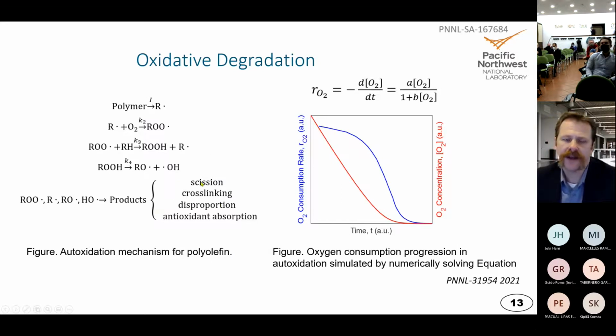In thermal and radiation aging as well, for these polymers, the major mechanism of degradation is oxidative degradation, where the polymers, the hydrocarbons, react with oxygen in the atmosphere, and reactive radicals get generated in the polymer from the radiation or from the heat, and those react to break up the polymers and change the mechanical properties. The major concern is that they embrittle the polymer, and then if there's an accident in the plant, they won't perform their function. The oxygen gets consumed in that reaction. So one measure of aging that's been proposed that might track closely with aging, even at mild aging, is the consumption of oxygen in this reaction. If you're having this oxidative degradation, it doesn't happen without consumption of oxygen. So the rate of oxygen consumed, if we're able to measure it, should tell us about what's happening.